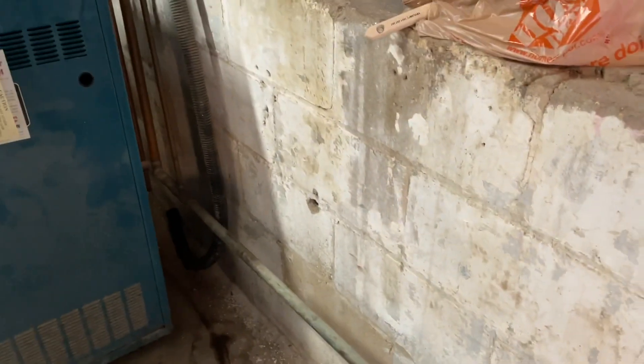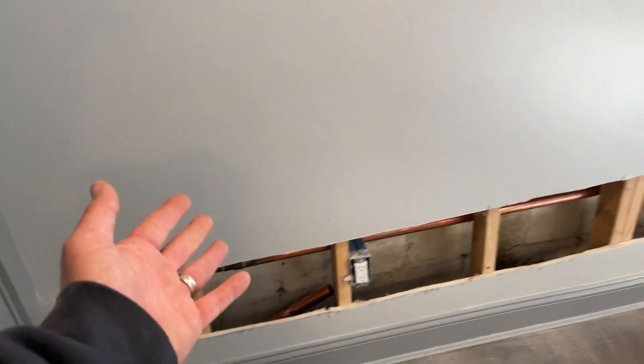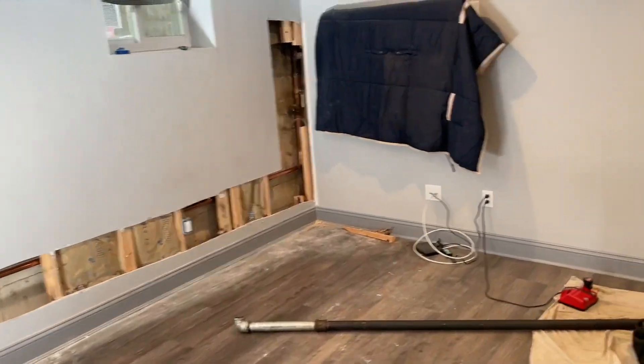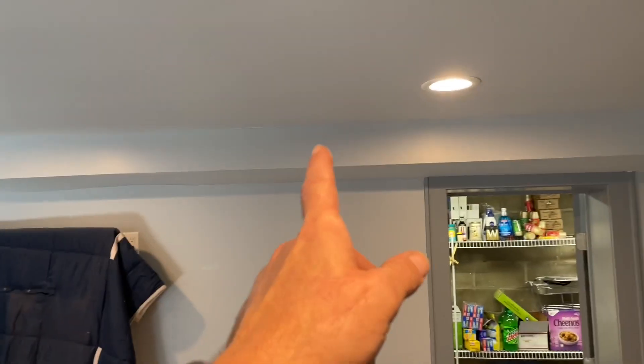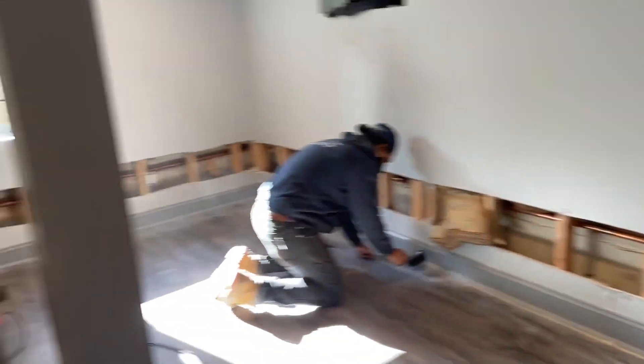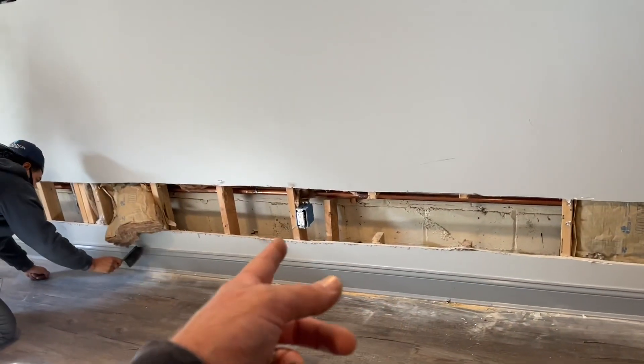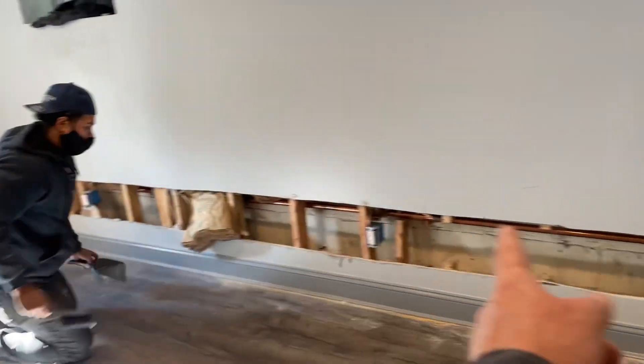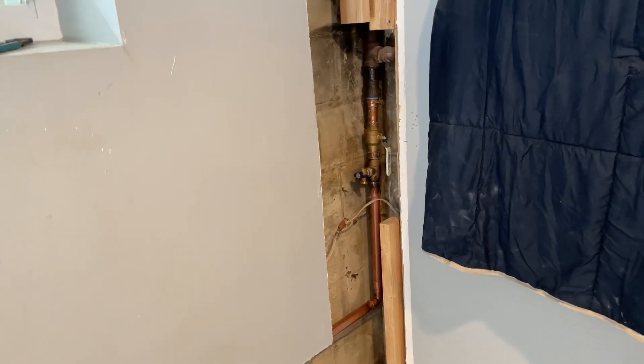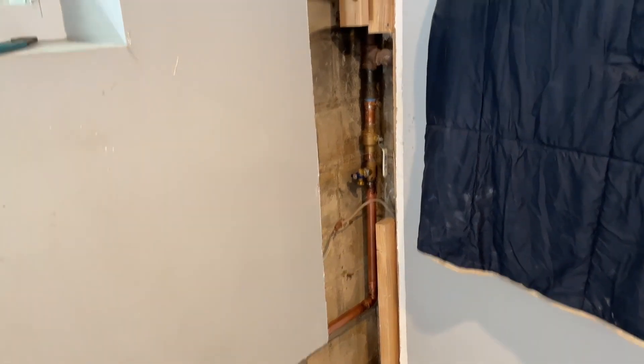To the boiler, as you can see right there. The customer's problem, like I said, was that when the steam is on, the house is violently banging, the piping is violently banging, and we have water coming out of the steam radiator air valves upstairs. The water just couldn't make its way back because the wet return was clogged. So we cut open the sheetrock wall and replaced the one-inch with inch and a quarter, and I used L copper instead of M — not necessary, but it's not much of a price difference for me, and the total cost of the job is insignificant.